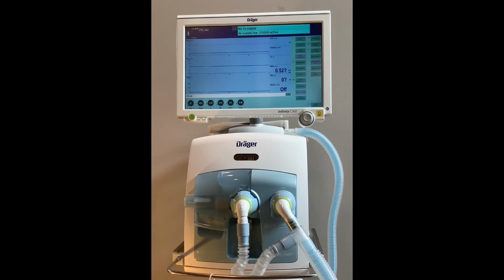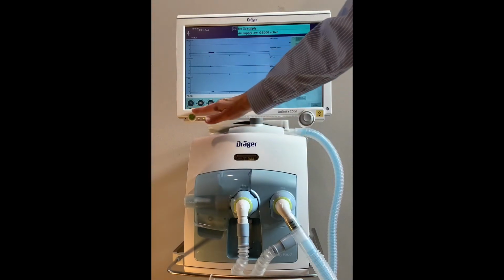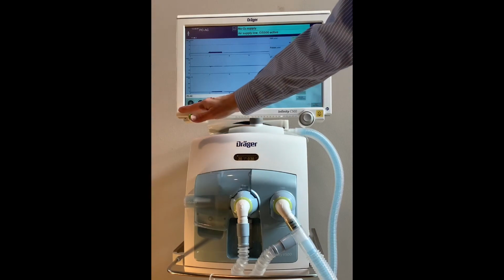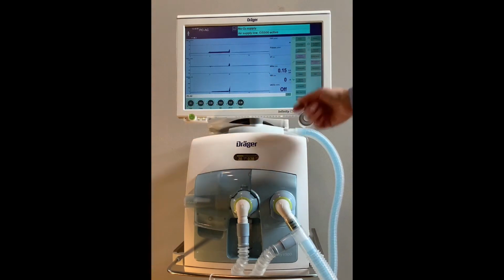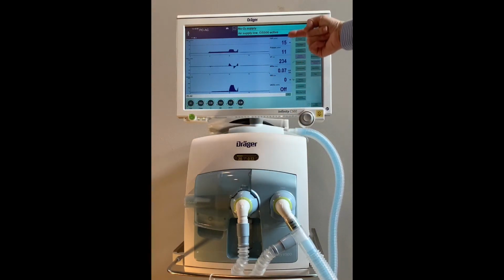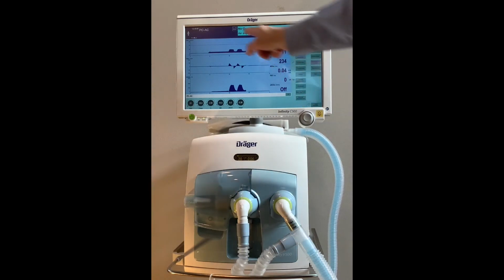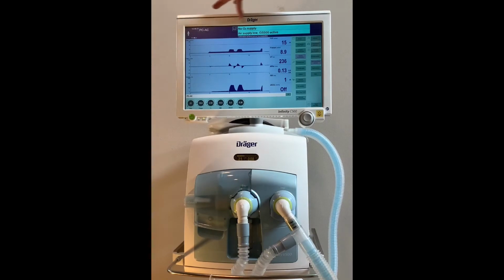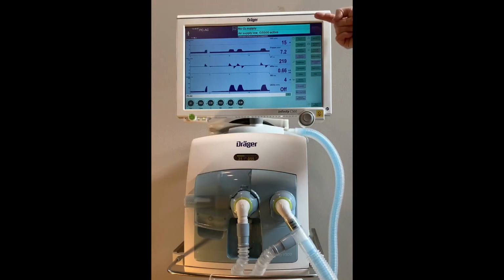While ventilating, the V500 will display the ventilation parameters in the buttons across the bottom of the screen. Any blue value displayed is a measured value. Graphics will be displayed in the center of the screen, and atop the header bar, you'll find your mode of ventilation and any alarm messages to the user.